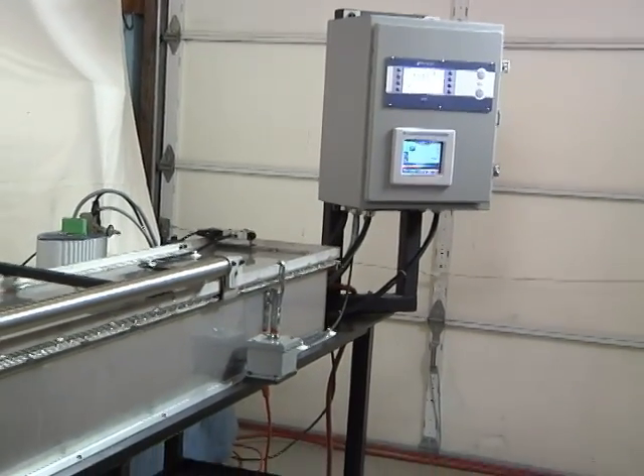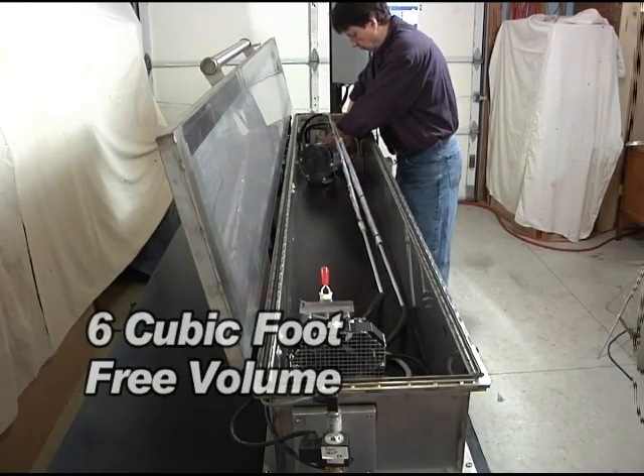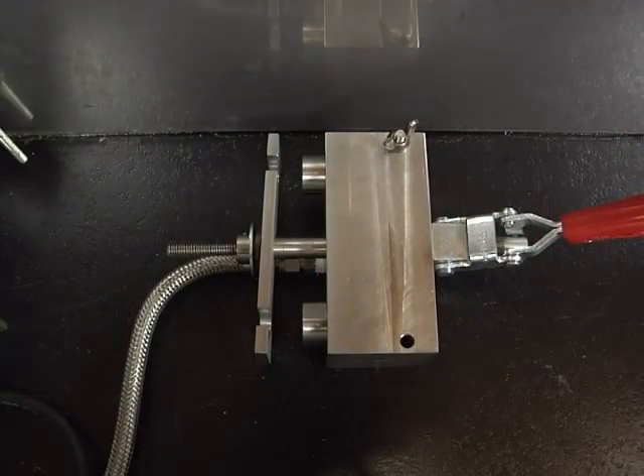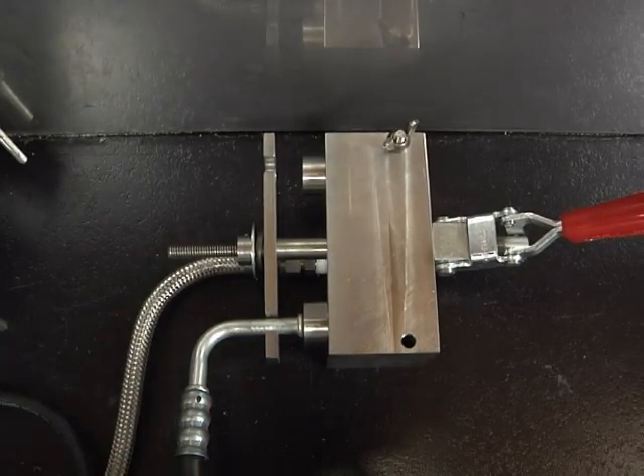The box has six cubic foot of free volume with manual load and unload features and utilizes a PLC to automate the sequence. The goal was to build the system and test two parts simultaneously with simple tooling. This allows for the operator to load the parts and clamp with minimal effort.